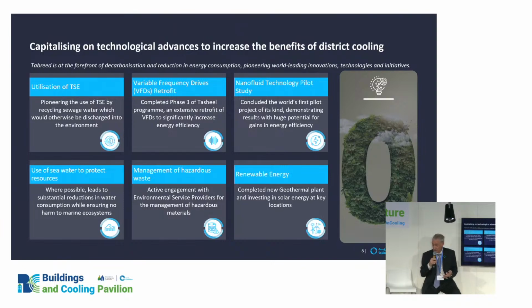Things like putting variable drives on our chillers - 25 years ago, a chiller was either on or off. So if it was a 2,000-ton chiller, it was producing 2,000 tons of chilling or no tons of chilling. Now we can vary that, so we can scale up the production out of a chiller to give you exactly what's needed. Again, that's a big efficiency gain.